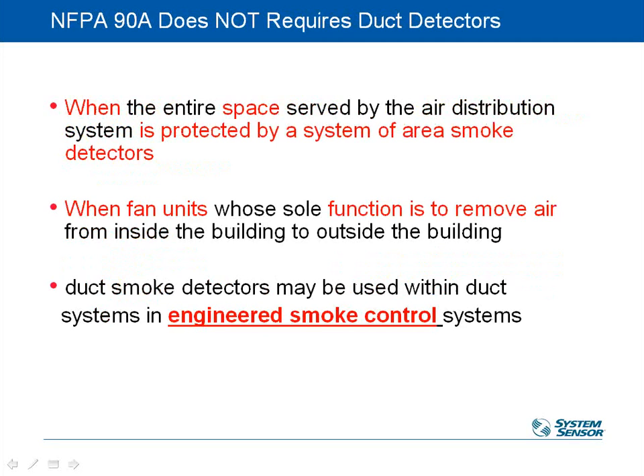When the entire space is served by the air distribution system, I should clarify what I'm talking about here. NFPA 90A does not require duct smoke detectors in these situations. When the entire space is served by the air distribution system that is protected by area smoke detectors, so you have a complete system, you don't necessarily have to have duct detectors as well, although oftentimes engineers will put them in. It's a good, inexpensive insurance policy.